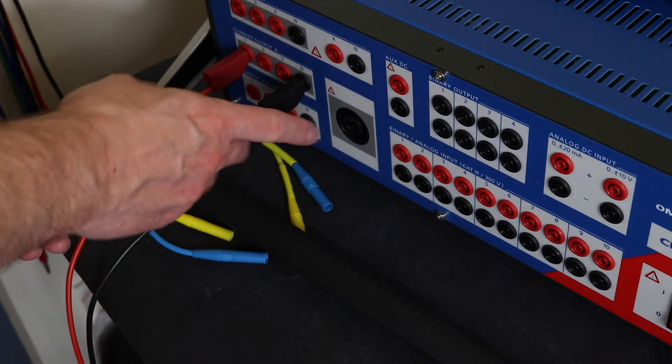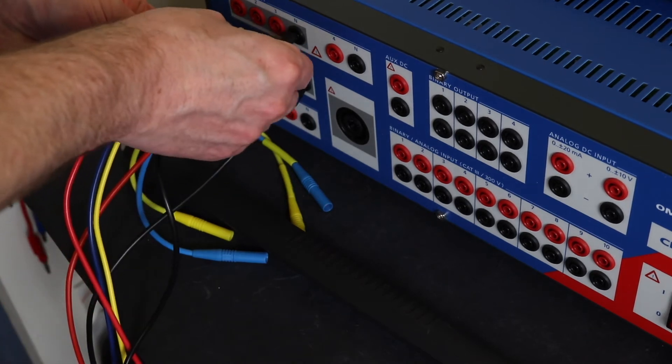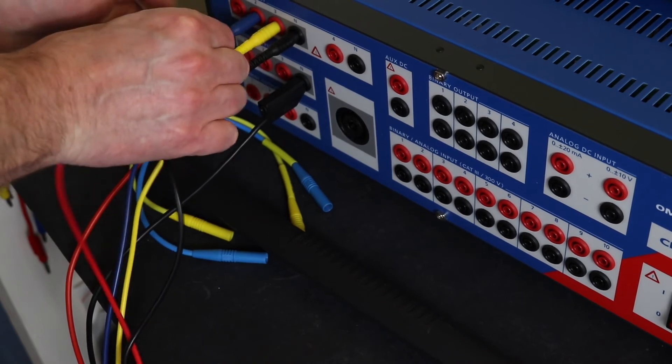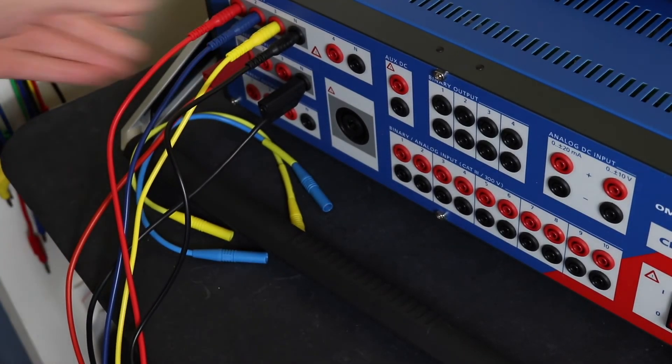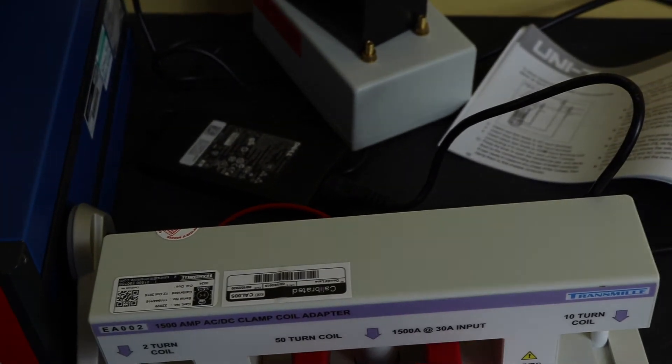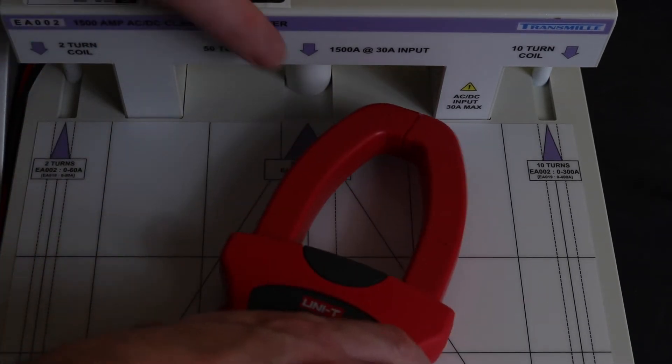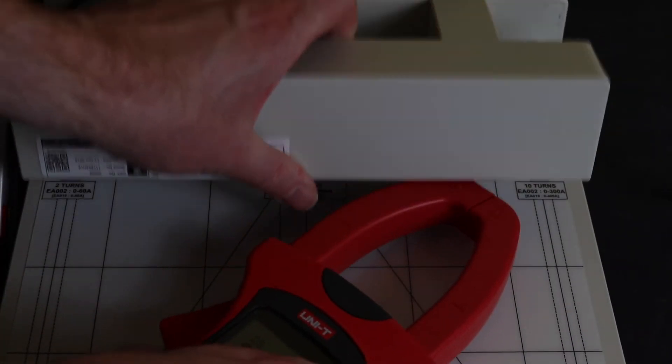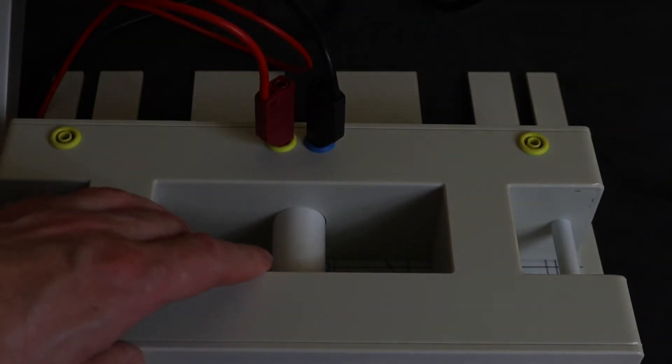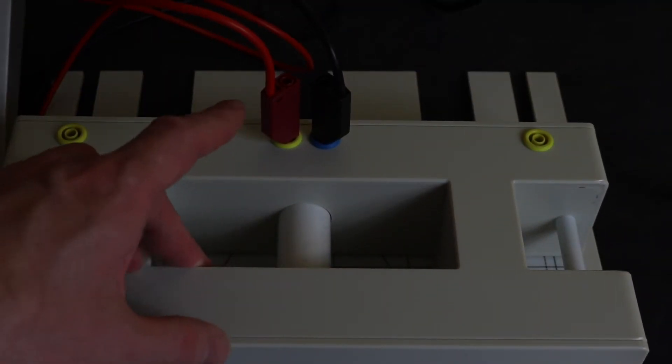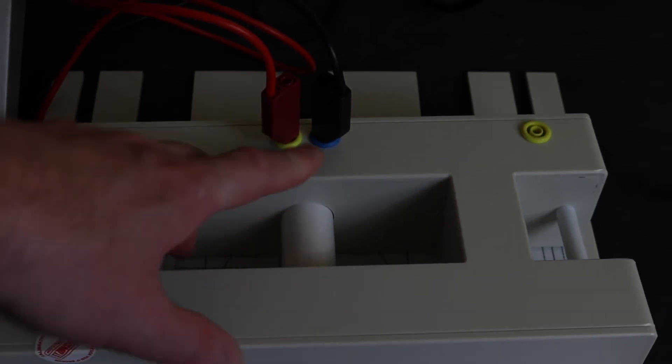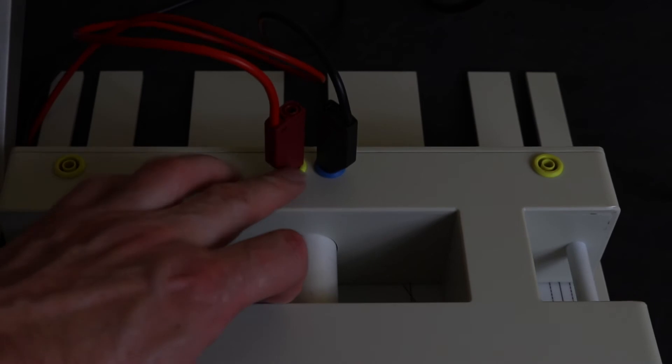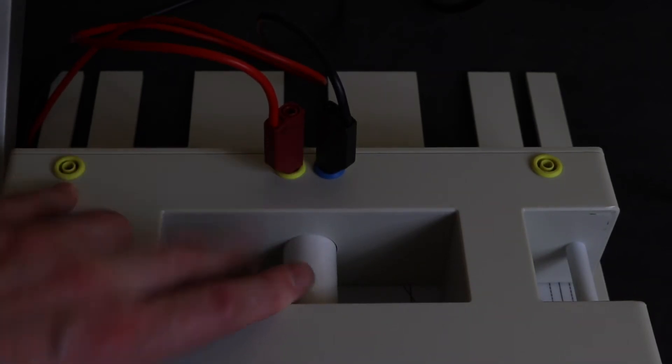live feed of the coil adapter and then the neutral there. Let's put these three back in. So, let me take you around - these are the connections to my coil adapter here. I've got neutral there, which is common to all three coils, and then each coil live termination is in the yellow jack. I'm plugged into the center one, which is the 1500 amp coil.